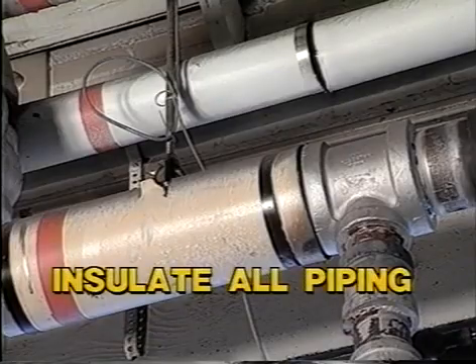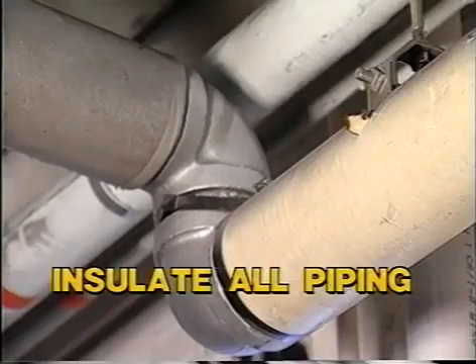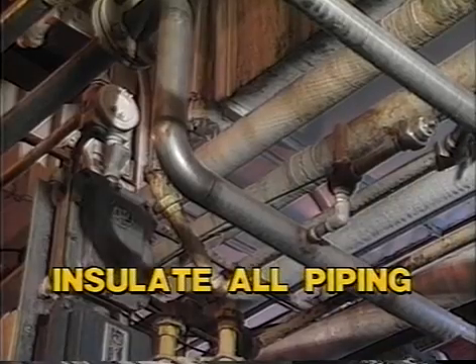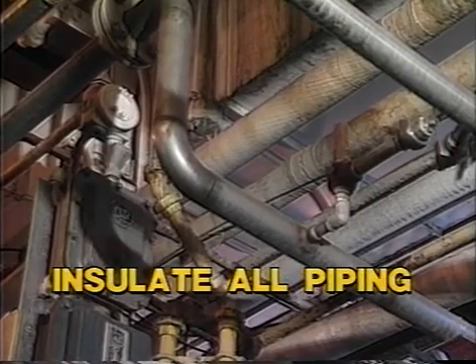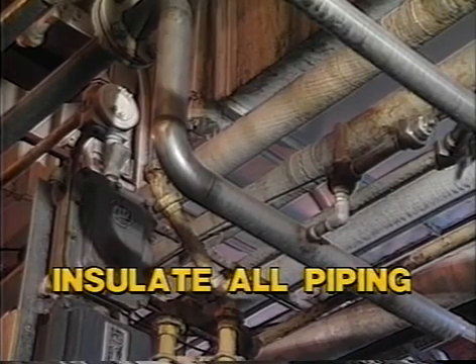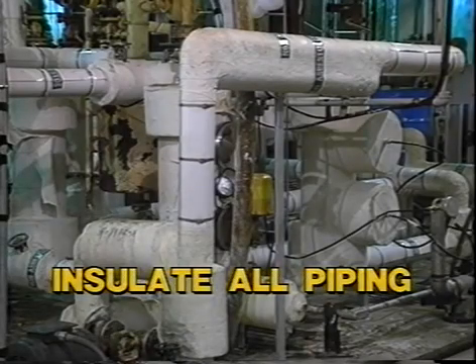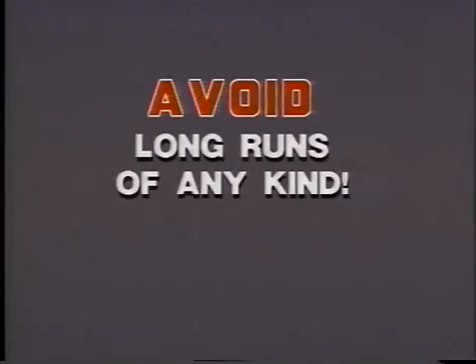In both of the two previous cases, the condensing of steam downstream of the seal produced the acceleration. It follows that the likelihood of differential shock arising and causing water hammer is greater in uninsulated pipes, especially on outdoor systems, than in insulated pipes. Long runs of any kind between the heat exchange equipment and the trap can produce this situation and should be avoided.